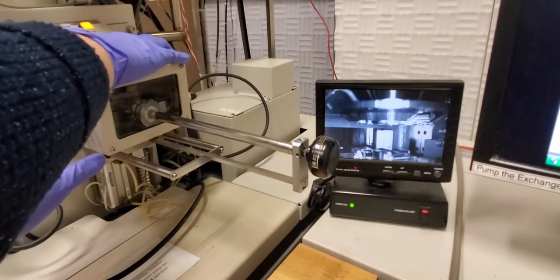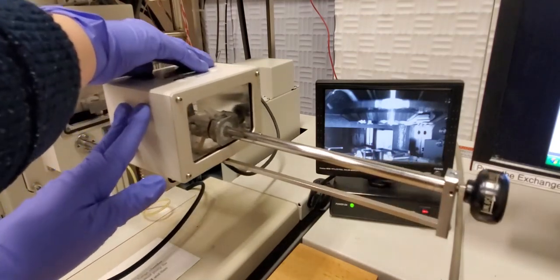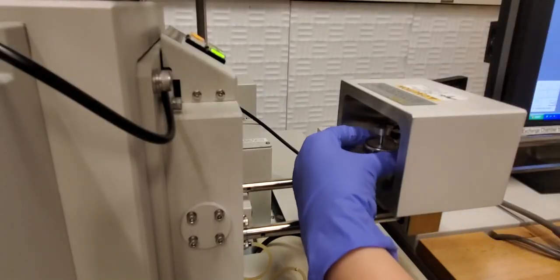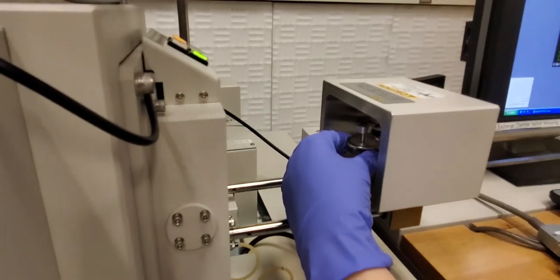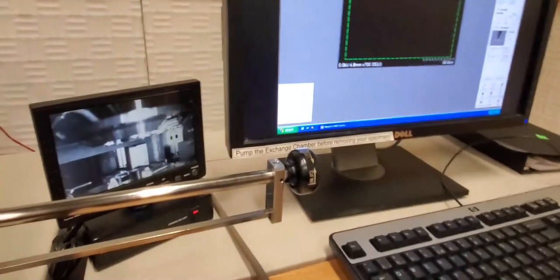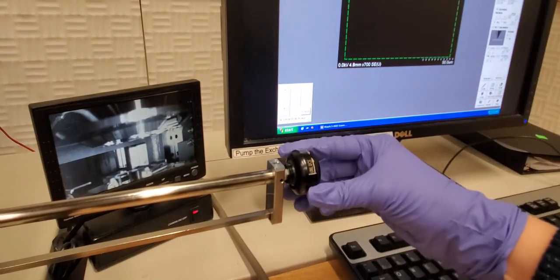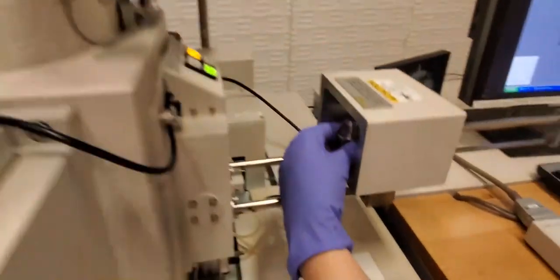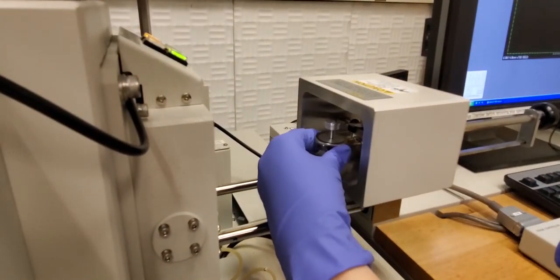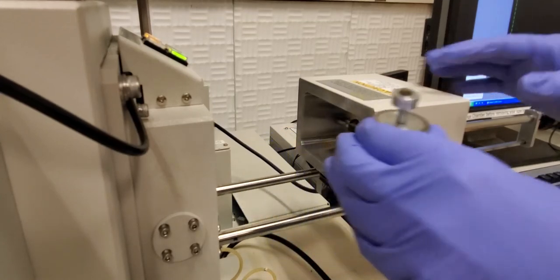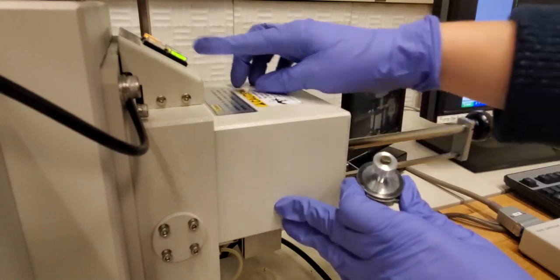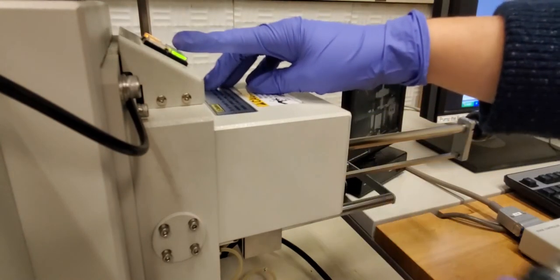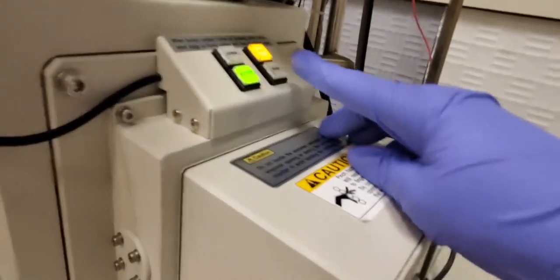We need to retrieve it so we're going to vent the chamber again. Use your hands on the box to open the sample chamber. You can grab the sample and make sure you unlock the loading bar and be gentle when you turn it. You don't have to turn it very hard. And now you can slide your sample off. Close the door and put it back under vacuum. Press the evac and here you can see a close-up of the buttons.